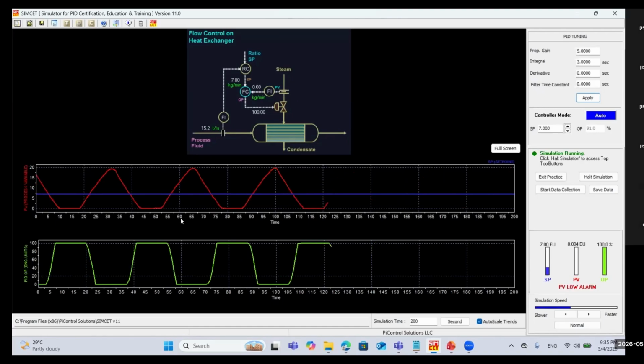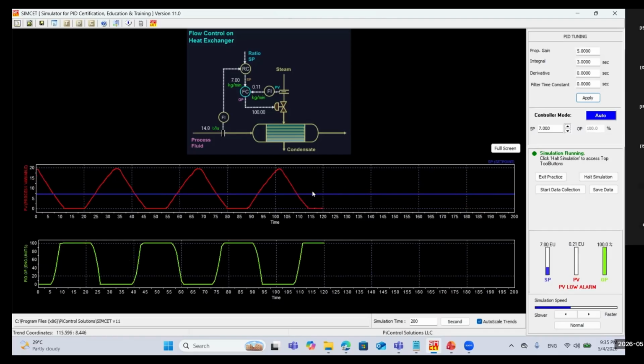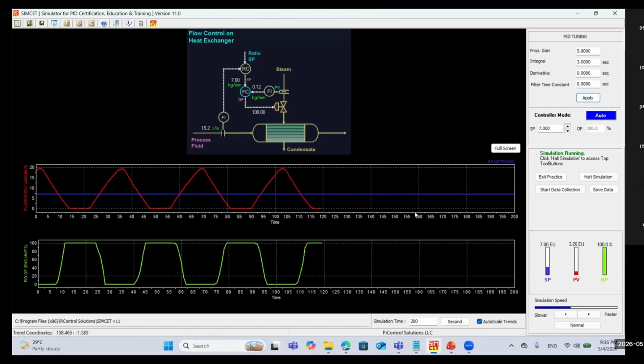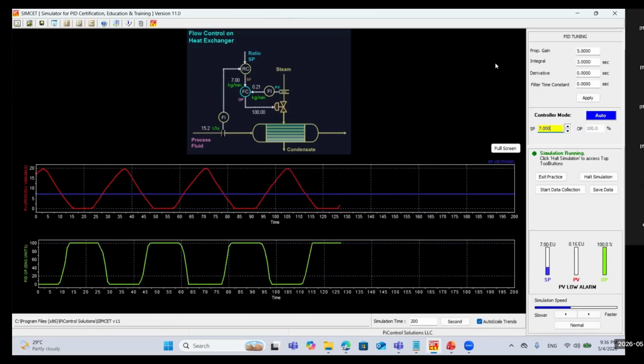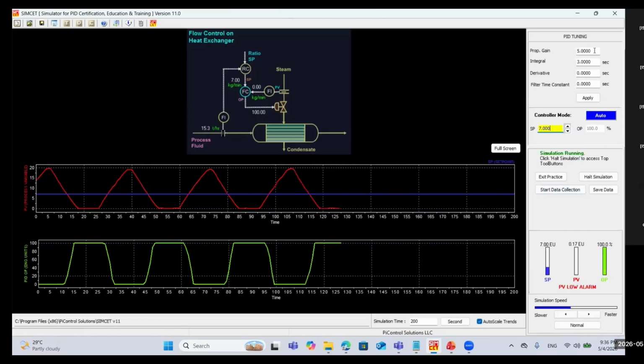What you can see here is our output, which is the valve, the green one. The red one is our PV, which is the flow. This is the flow of the steam, and this is the valve. So you can see it is hunting. It is oscillating. Since this is a flow controller, you can see here my proportional gain parameter is 5, my integral is 3, my derivative is 0. I have no filter.